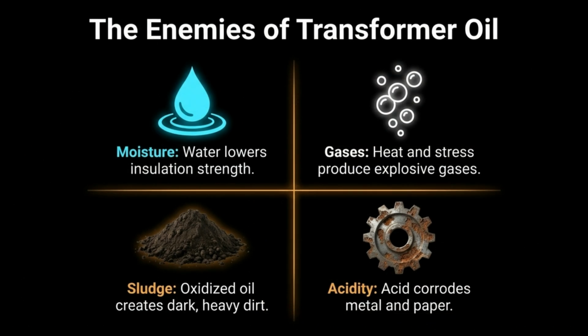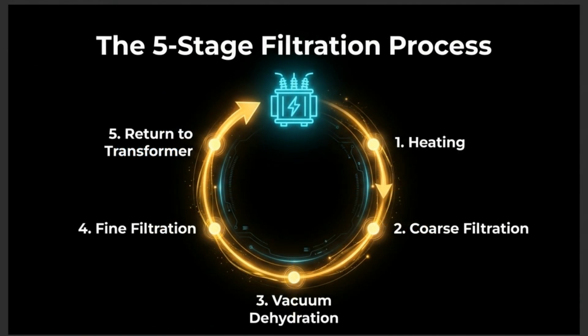The enemies of transformer oil include moisture, which lowers insulation strength, and gases, which can become explosive. Sludge and acidity also damage the internal components. Transformer oil is cleaned through a 5-stage filtration process: heating, coarse filtration, vacuum dehydration, fine filtration, and finally, returning the oil to the transformer.